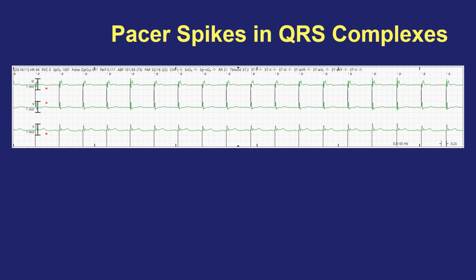Well, just like a permanent pacemaker, there's a setting called the AV delay. That is the amount of time that you tell the pacemaker to wait after it sees a P wave to decide whether conduction is occurring and whether it needs to pace in the ventricle. And that number can be increased or decreased. And in this case, the AV delay is set at too short a number. We're not giving enough time for the pacemaker to see if native conduction is occurring. And in fact, it's just about a tie. Just at the time that conduction is occurring, the pacemaker's little AV delay clock elapsed, and it said that it needs to pace.